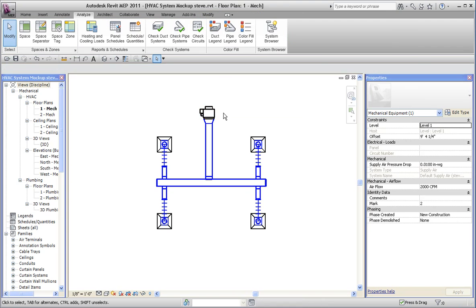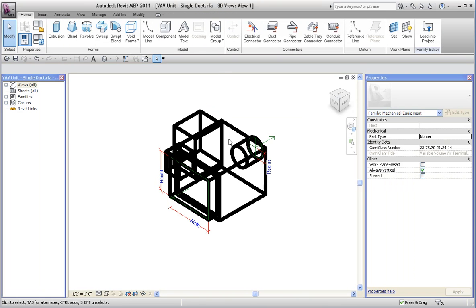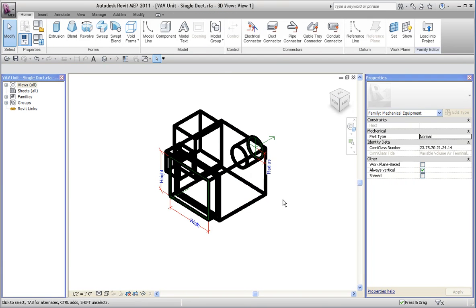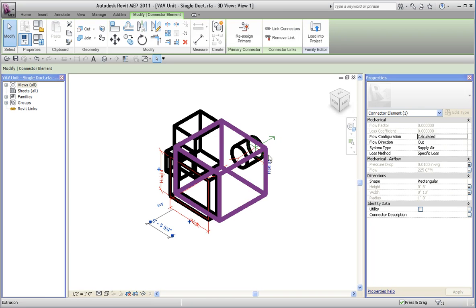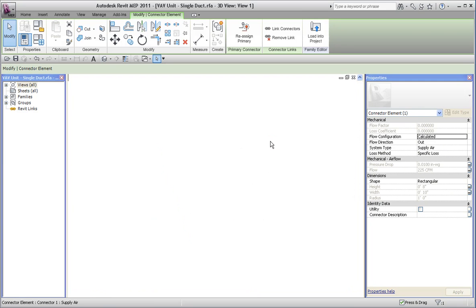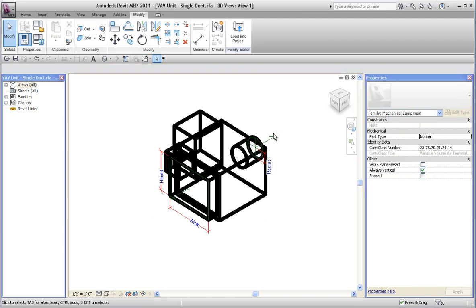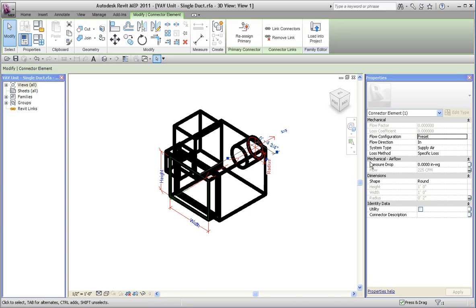Now interestingly enough, if I look at the properties of the family or look at the construction of the family, when I select these connectors, there's a link between this connector and that connector. And if I look at this connector, this is the supply air side, the inside. Notice it's set to preset. And that makes sense because I'm going to set this so that it pushes a value up to the air handler.